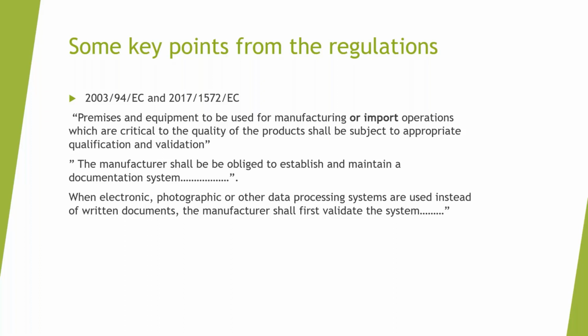It also says the manufacturer shall be obliged to establish and maintain a documentation system. So we're talking about having the necessary documentation in the form of SOPs, etc., and records that you are going to be making of the analysis that you perform.